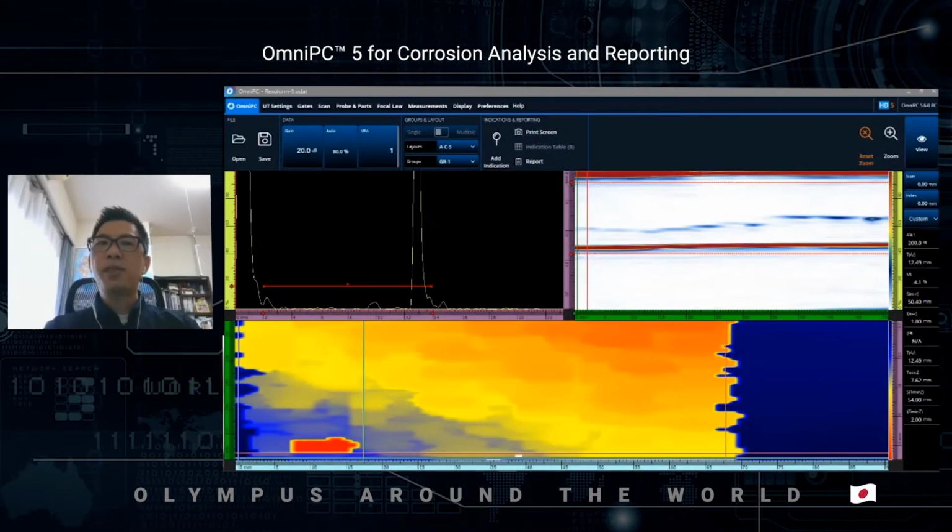The analysis starts from the optimization of the C-scan, which consists of optimization of the color palette and optimization of the gate position. The color of the C-scan indicates the approximate range of the thickness readings. In this data, it contains color from red to blue, meaning the contrast of the C-scan is optimum between the thinnest part and the thickest area. But you can edit the palette very easily if necessary by specifying the start and end point of the palette.